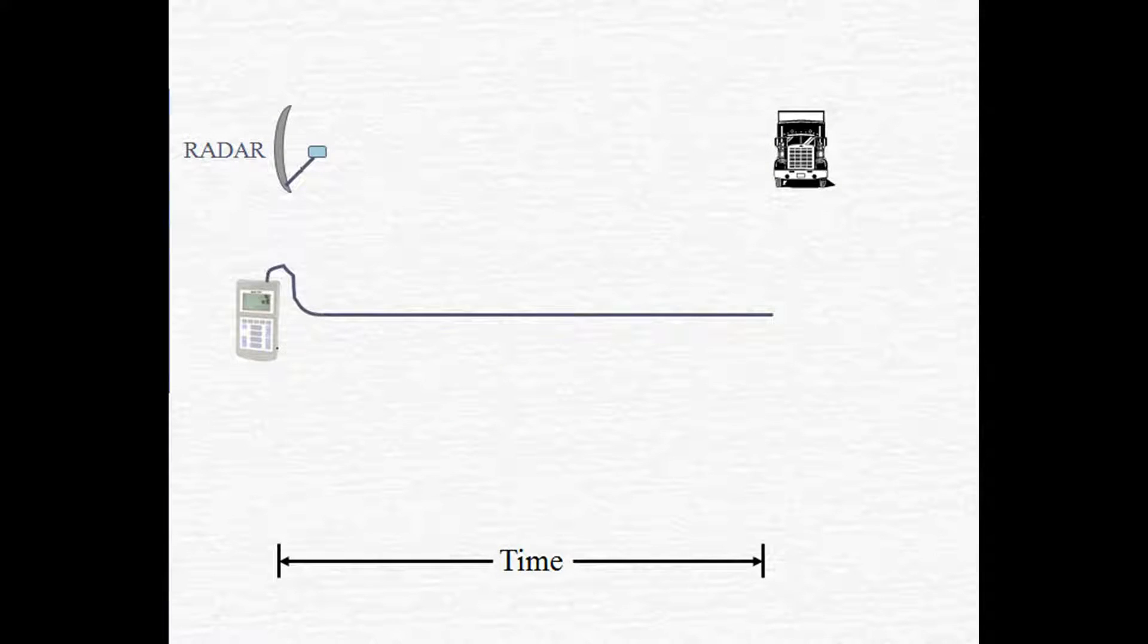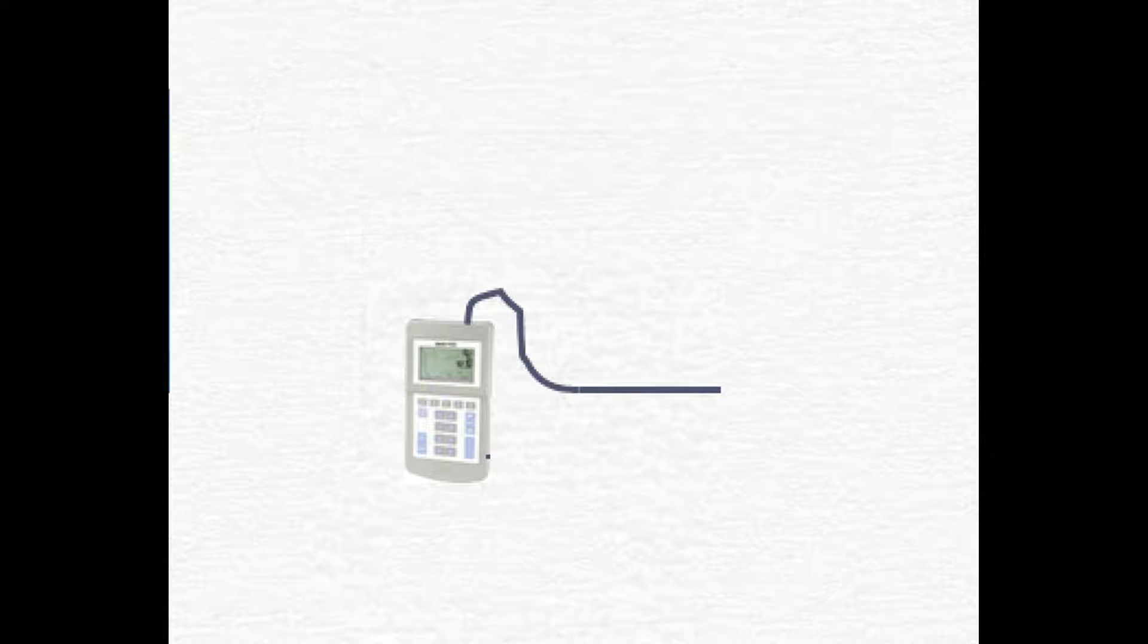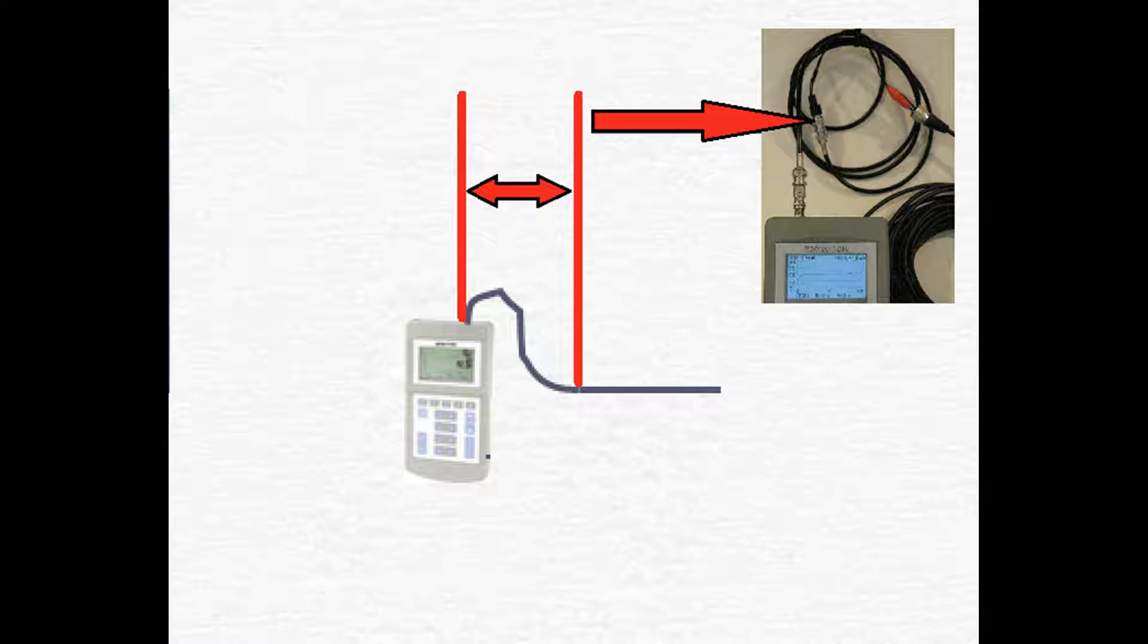A TDR does the same thing, but instead of using a radio wave, it sends an electrical impulse. The pulse travels down the wire, strikes the fault, then returns. Since you're dealing with wire instead of open air, an accurate measurement requires you to consider a few other factors. The first is, the test set is hooked up using test leads. Since your electrical pulse travels down the test leads before getting to your cable, the length of the leads will be included in your distance. All TDRs that I've ever used give me a software option to eliminate the test lead error.